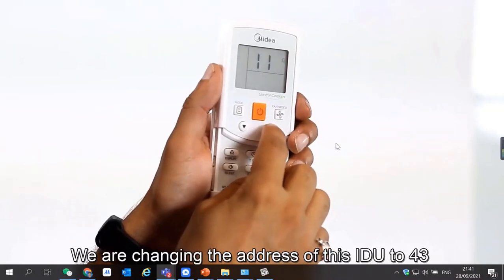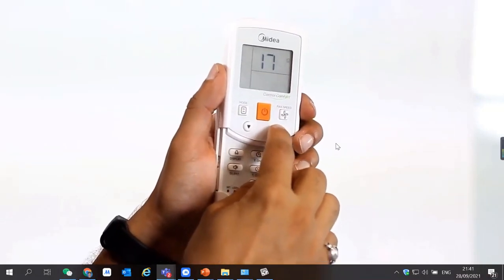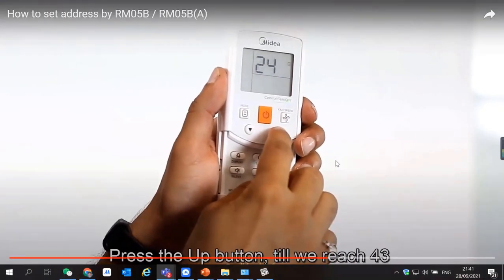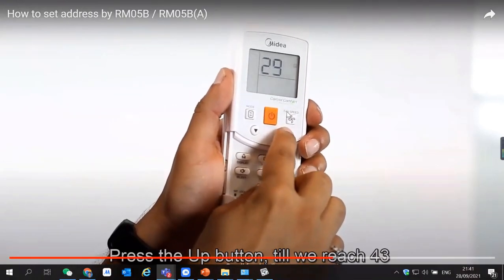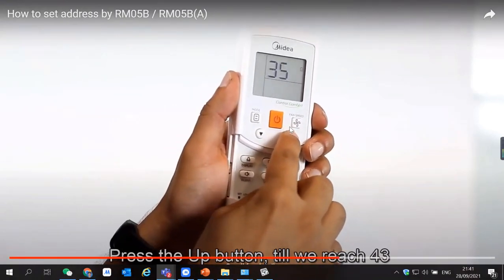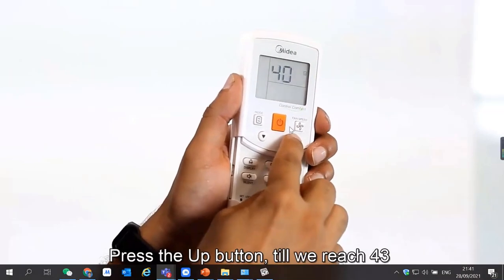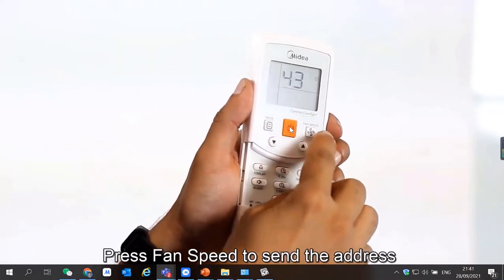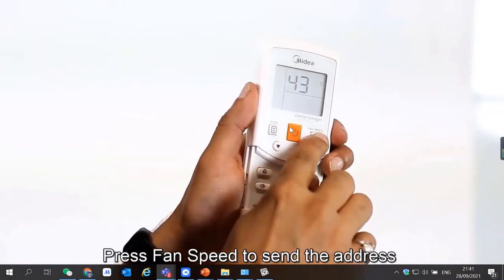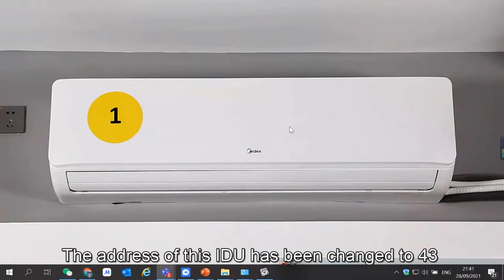So right now I'm changing this to maybe 43, and once we go to the 43, then we will use the fan speed to send this address to the indoor unit side. So here we go to the 43 and then press the fan speed. So now the address of this indoor unit is 43.